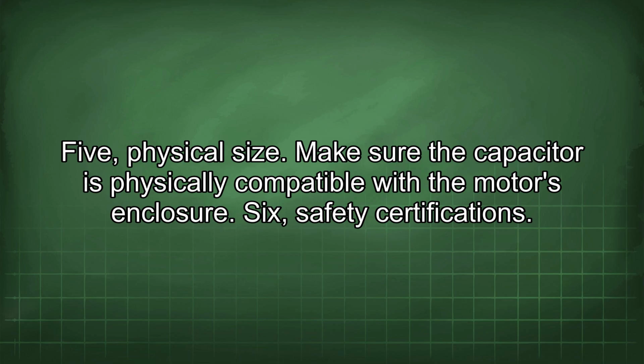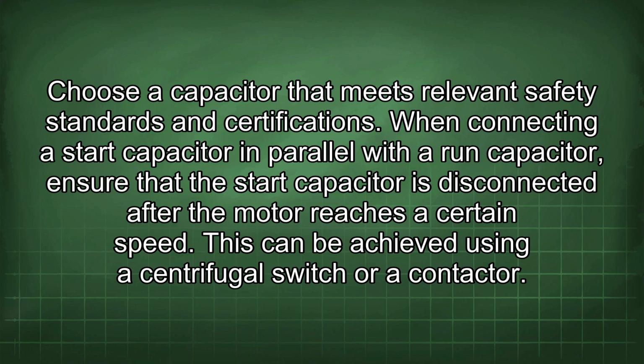Make sure the capacitor is physically compatible with the motor's enclosure. 6. Safety certifications. Choose a capacitor that meets relevant safety standards and certifications. When connecting a start capacitor in parallel with a run capacitor, ensure that the start capacitor is disconnected after the motor reaches a certain speed. This can be achieved using a centrifugal switch or a contactor.